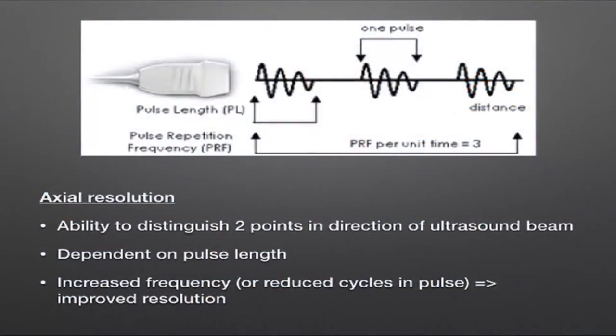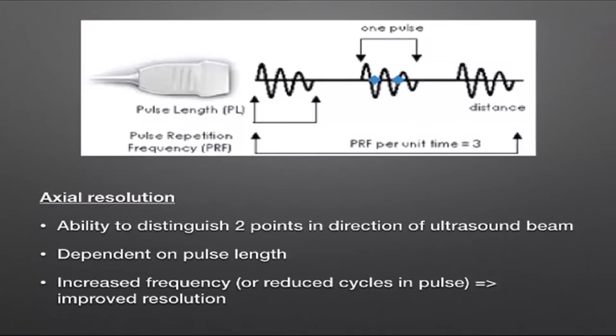An important parameter is axial resolution — our ability to distinguish two points that are close together in the axial plane, the direction the ultrasound is travelling in. The ability to distinguish two points separated in the axial plane is dependent on the pulse length. If these two points are closer together than the pulse length, the ultrasound machine will not be able to distinguish them as separate.